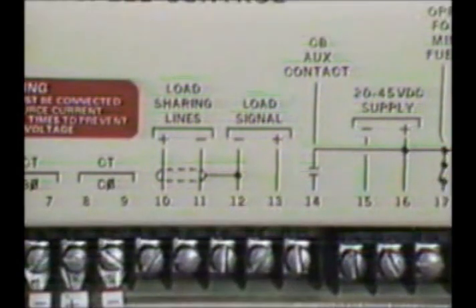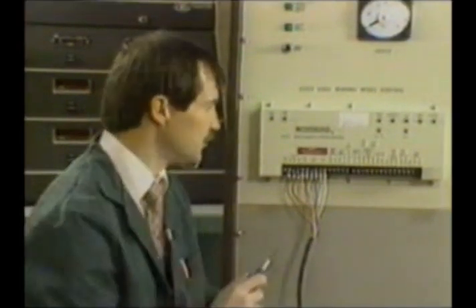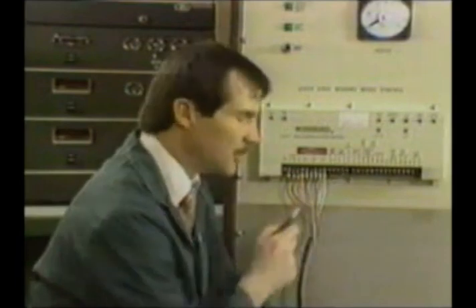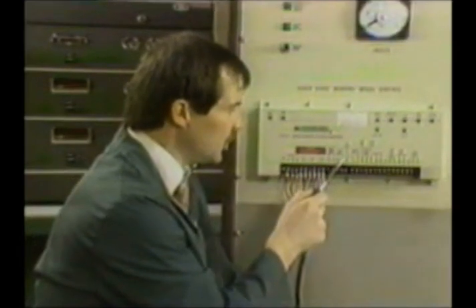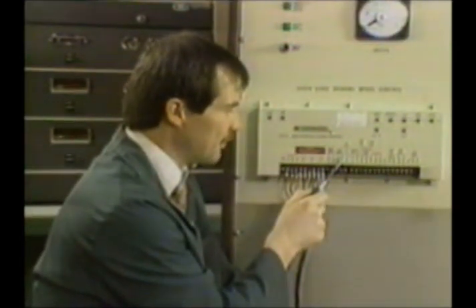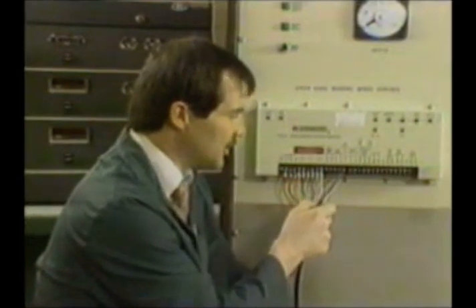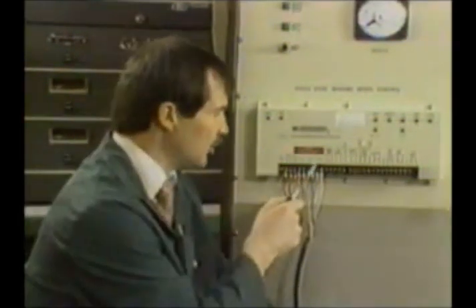Terminal 14 now is a new one. It's called a circuit breaker auxiliary contact. And what this does, it also provides you with an isochronous or droop control. If no voltage is hooked on terminal 14, you're going to be in droop control. And what we want the customer to do here is provide a relay or a contact of some type that will close when you go onto the load bus or your paralleling bus. Once on that load bus, that will close and that will put the 24 volts or whatever your input voltage is on terminal 14 to put the control in isochronous speed control. That will also close this relay in your load sharing line so you can isochronously load share.